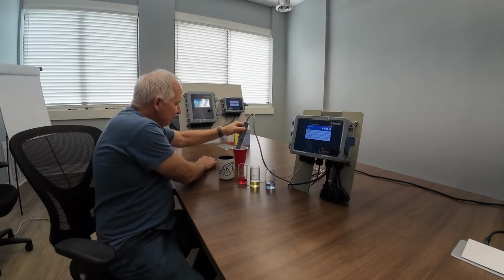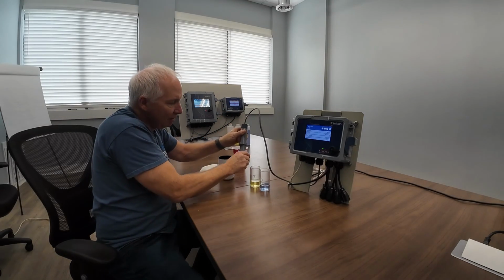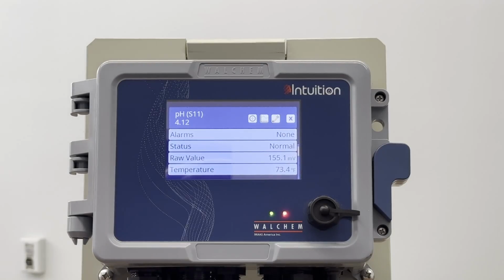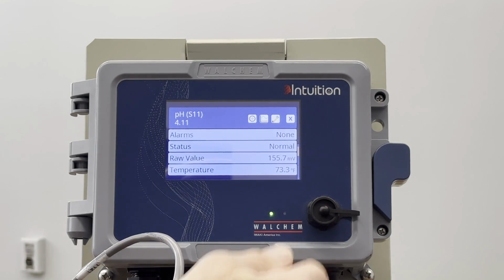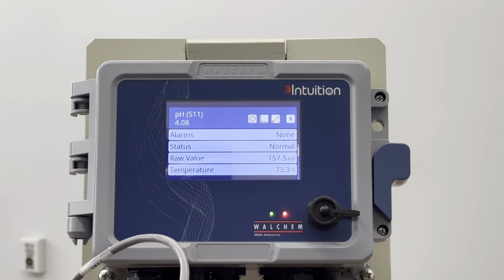So 59 millivolts from 7 to 4, which is 3 units, would be 59 times 3, which is 7 minus 4. That should be around 177 millivolts. So if I take this sensor and I put it in a pH buffer of 4, I should get somewhere around 177 millivolts, theoretically. So you can see on this controller, I'm getting somewhere around 158. That's not bad. If it's within 30 or 40 millivolts on that, it's going to calibrate, it'll be fine.